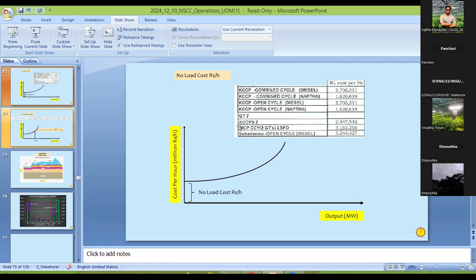So let's move on quickly. There are basically two parts in thermal dispatch: one is unit commitment, and the other is economic dispatch. Unit commitment means considering when machines are starting and stopping. Economic dispatch is that once you have started the machine, during its operation, how you are going to minimize the cost.